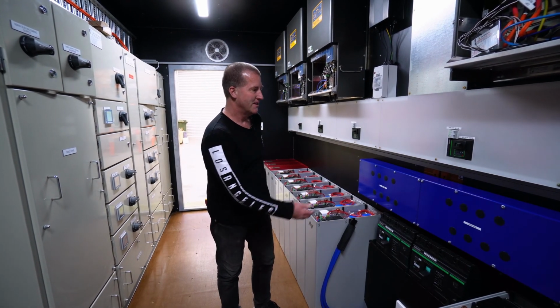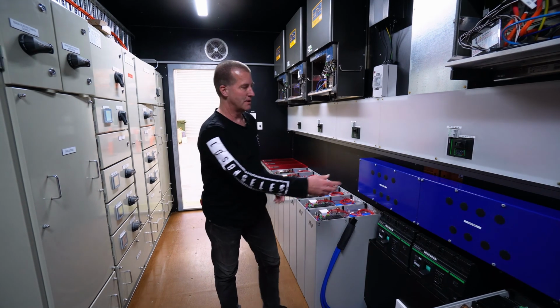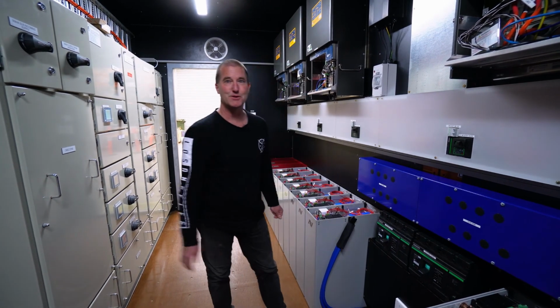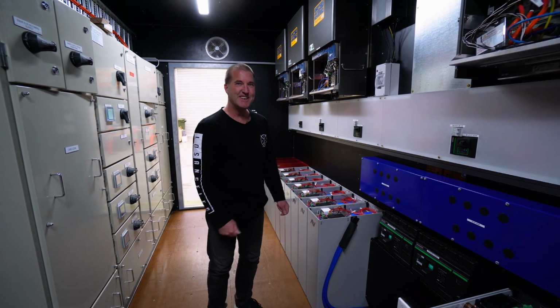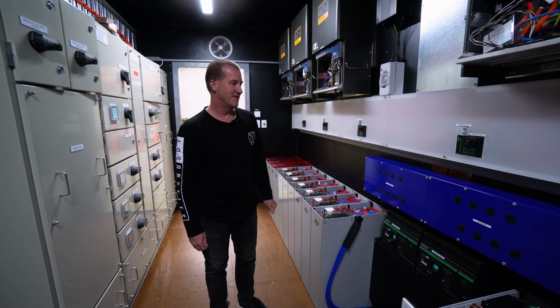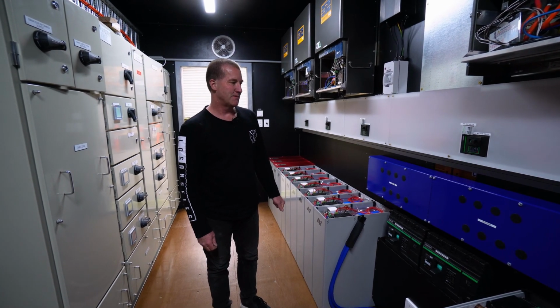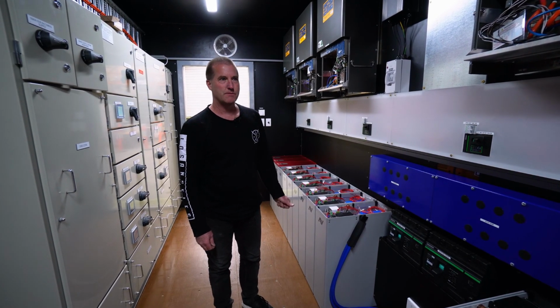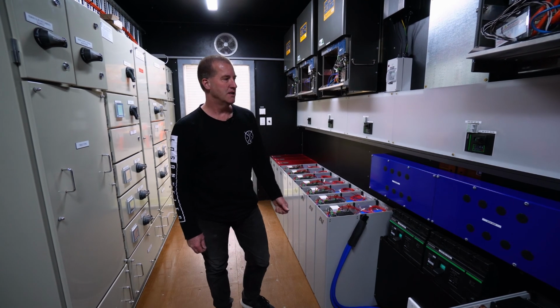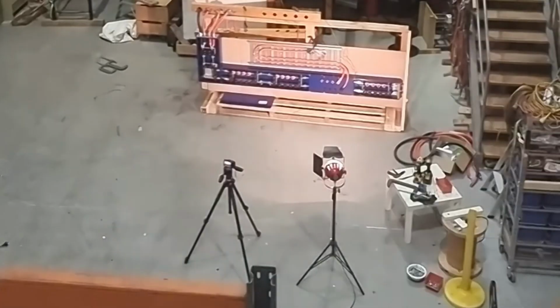So we took the fuses out and put copper bars in instead where the fuses were, like putting a nail in your fuse at your switchboard, and then short-circuited it. 50,000 amps, 800 volts, some enormous amount of energy, and it just blew the cables off the wall. But, wow.